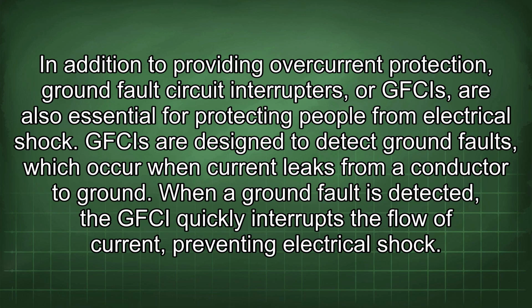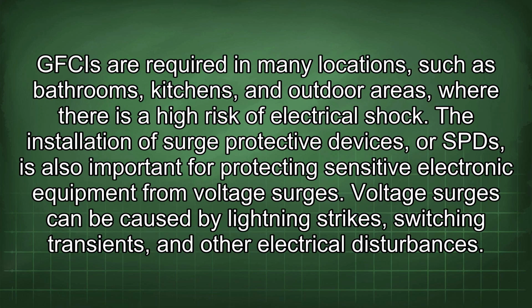In addition to providing overcurrent protection, ground fault circuit interrupters, or GFCIs, are also essential for protecting people from electrical shock. GFCIs are designed to detect ground faults, which occur when current leaks from a conductor to ground. When a ground fault is detected, the GFCI quickly interrupts the flow of current, preventing electrical shock. GFCIs are required in many locations, such as bathrooms, kitchens, and outdoor areas, where there is a high risk of electrical shock.